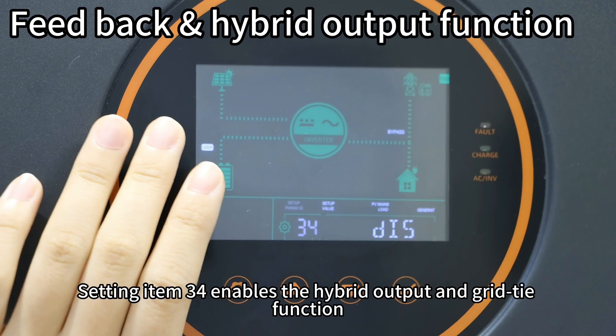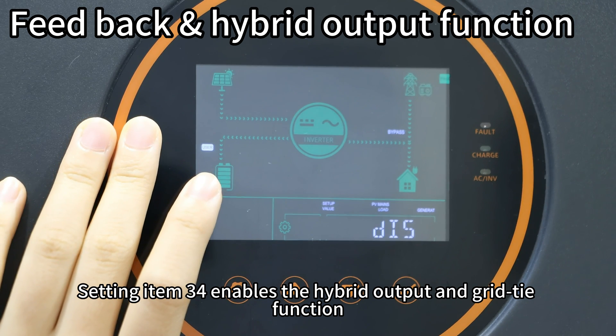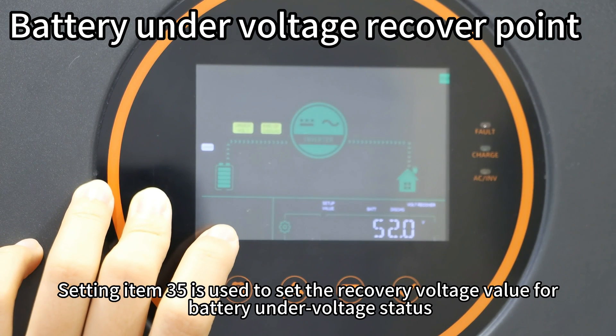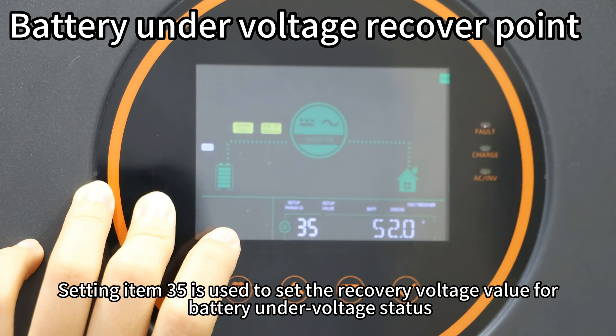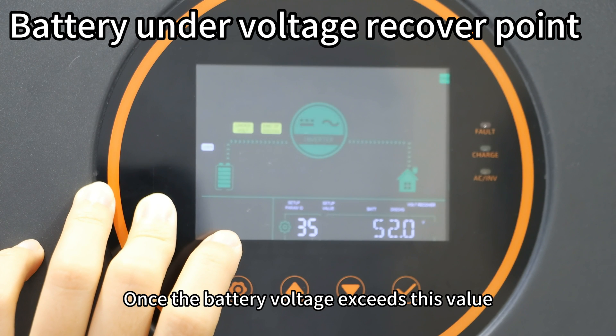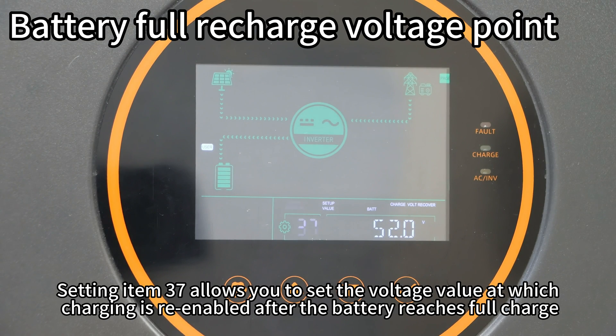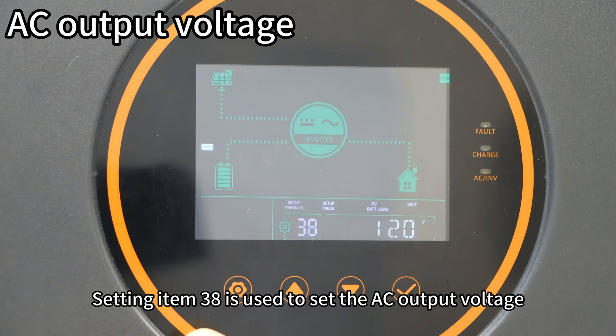Setting item 34 enables the hybrid output and grid-tie function. Setting item 35 is used to set the recovery voltage value for the battery under-voltage status — once the battery voltage exceeds this value, automatic discharge recovery will occur. Setting item 37 allows you to set the voltage value at which charging is re-enabled after the battery reaches full charge. Setting item 38 is used to set the AC output voltage.